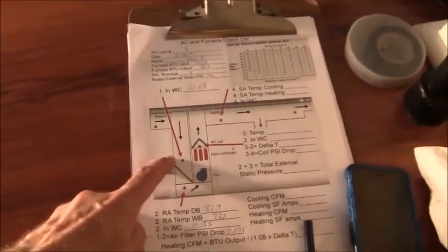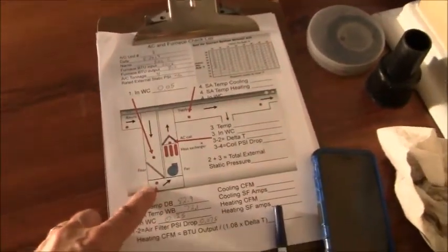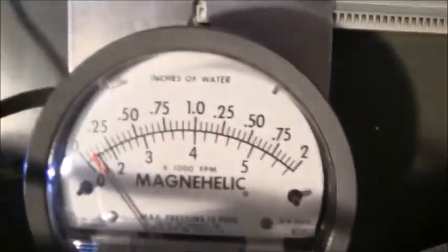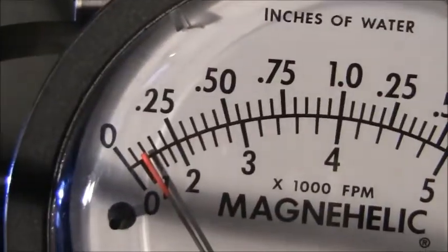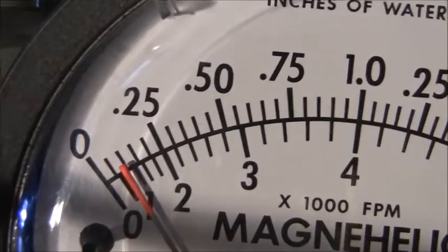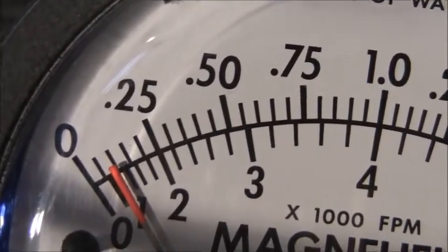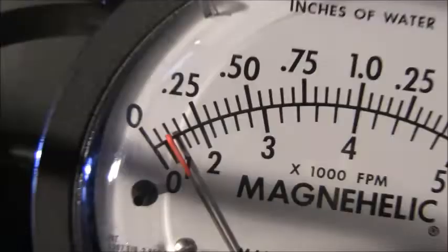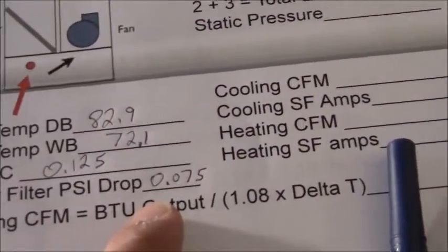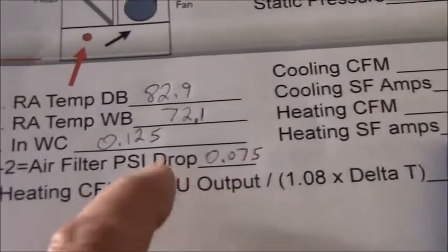Okay, I got it hooked up so that the high probe is actually here on the system, and the low probe is here. The reason that's a low probe is it's the lowest pressure on the system. It's just before the fan. Now, when I do that, this is what the reading is. It looks like it's 0.08. My mathematical reading on here is 0.075, pretty much the exact same number, okay?